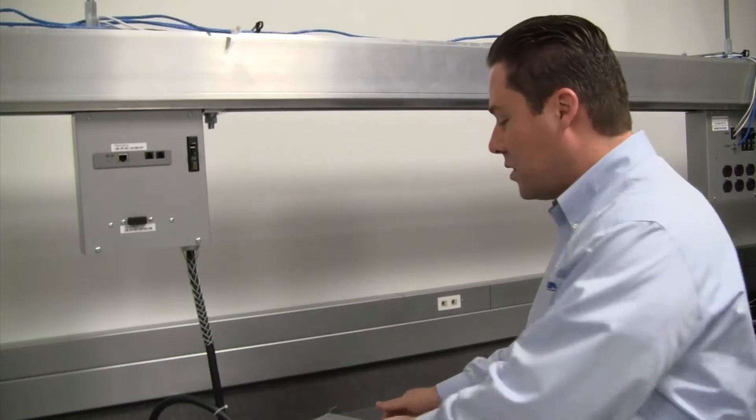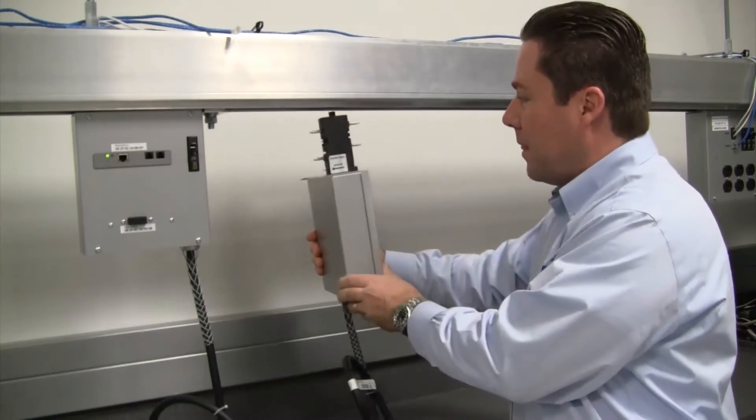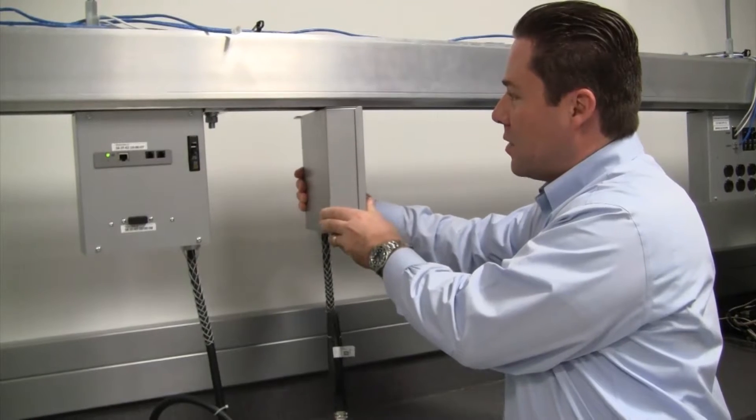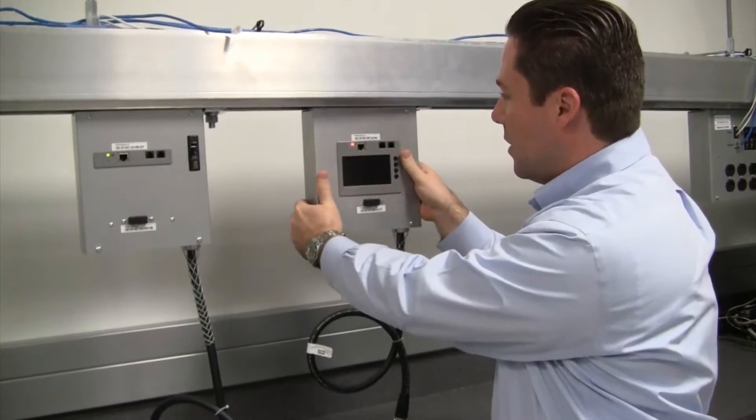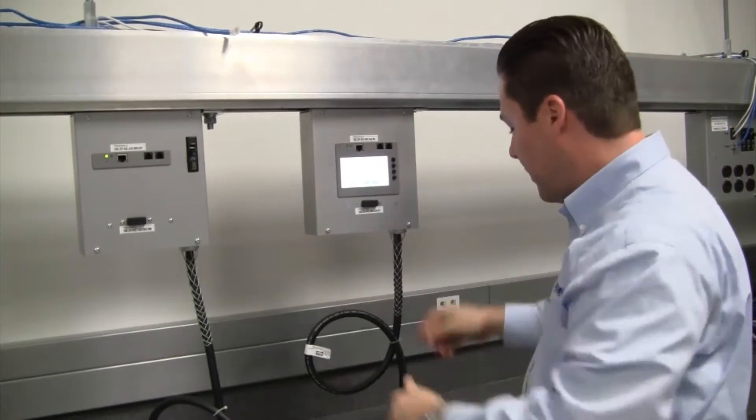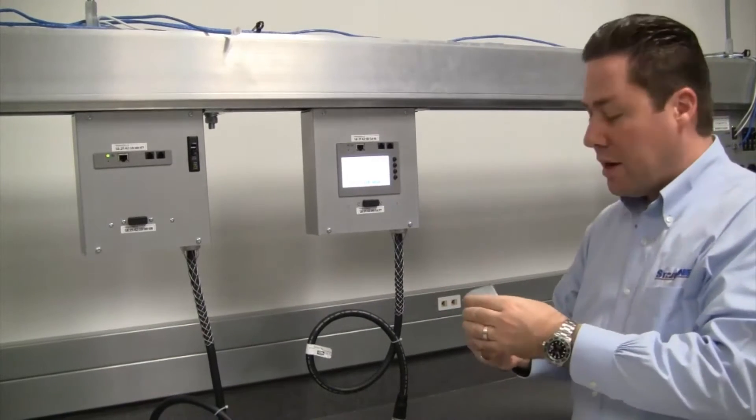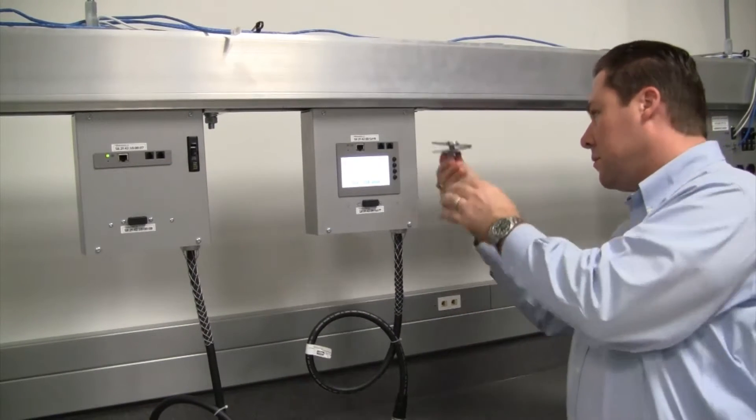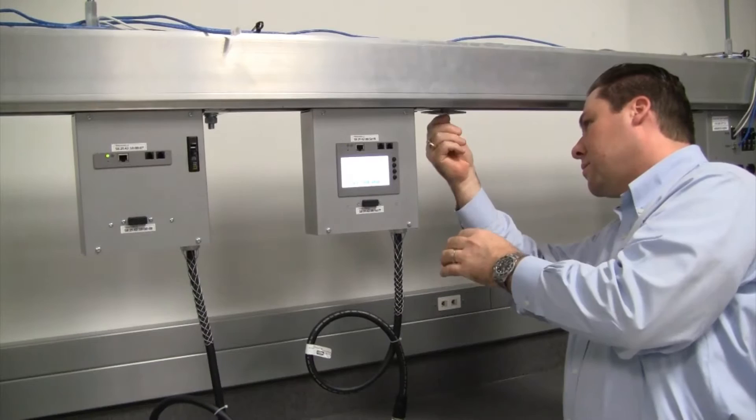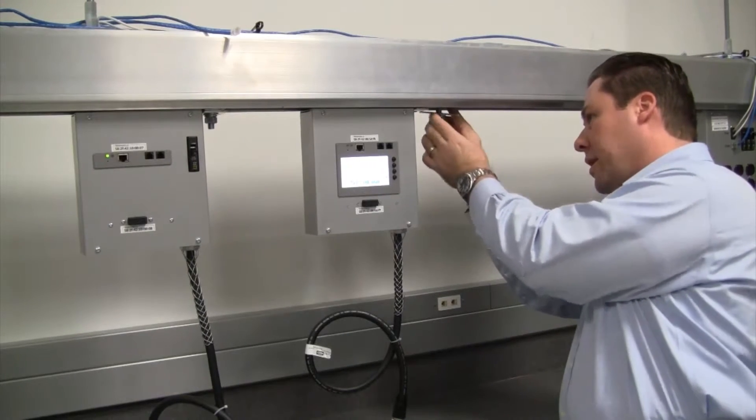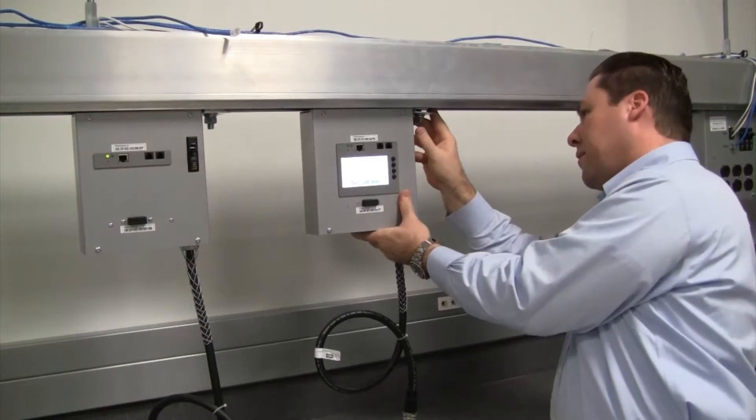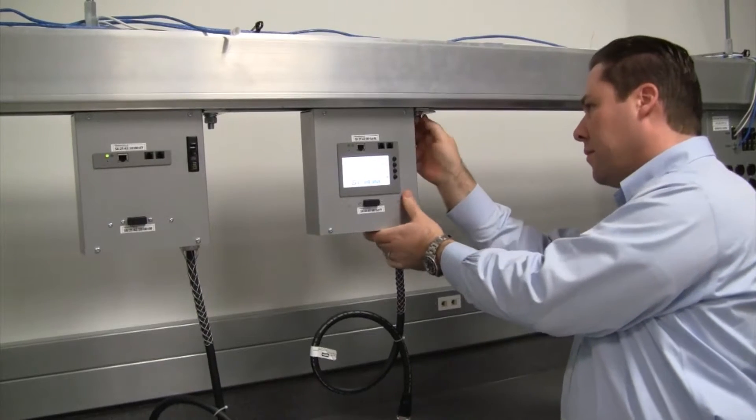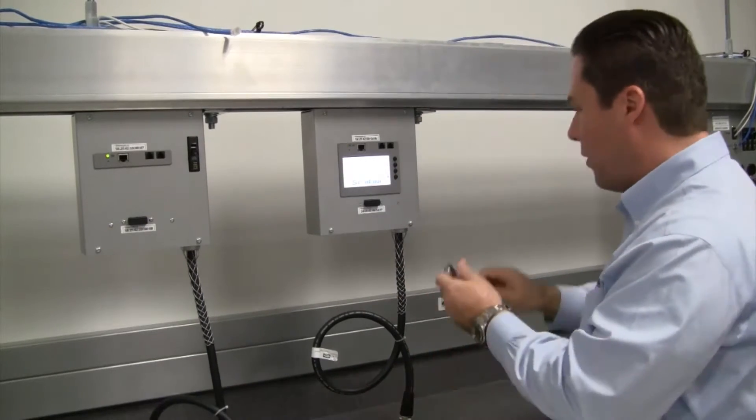To install the Starline plug-in unit into the busway, you actually insert the paddle into the busway, turn this towards you, take our hanger bolt, insert it into the appropriate channel in the busway, and then tighten up using a wrench.